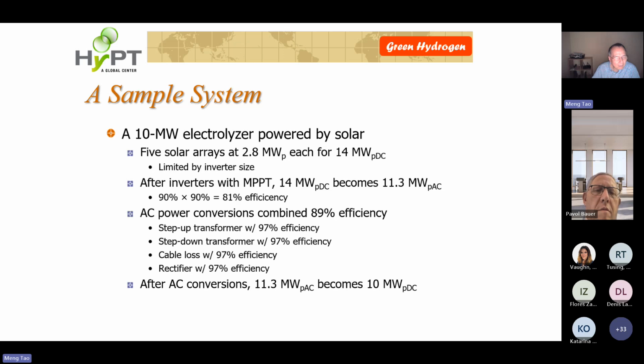Then after maximum power point tracking, we lose 10%. After inversion, we lose another 10%. So after the inverter, 14 megawatt becomes 11.3 megawatt AC. Then we have all the AC conversions: step-up transformer, step-down transformer, cable, rectifiers. Total, they lose about 11% of the energy. So after AC conversions, 11.3 megawatt AC becomes 10 megawatt DC. So you can see we started with 14 megawatt DC and now we end up with 10 megawatt DC. So 4 megawatts is just lost in all the power conversions.